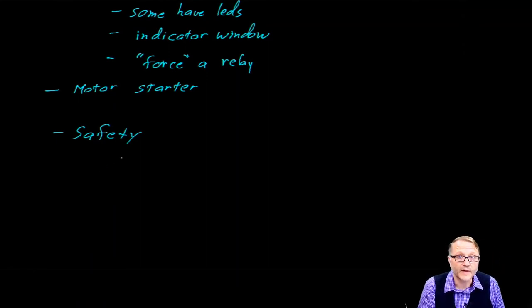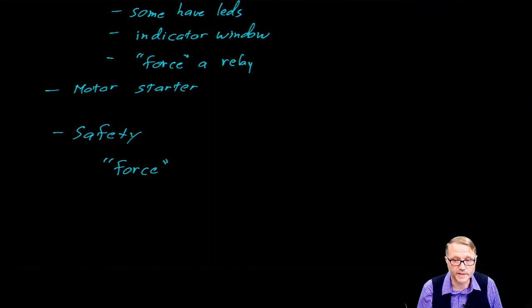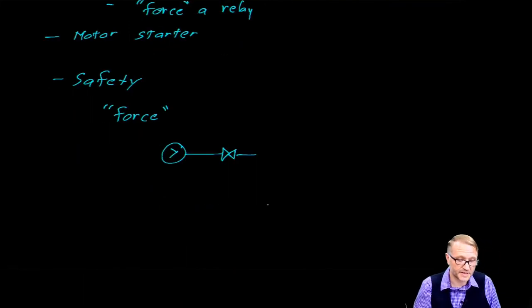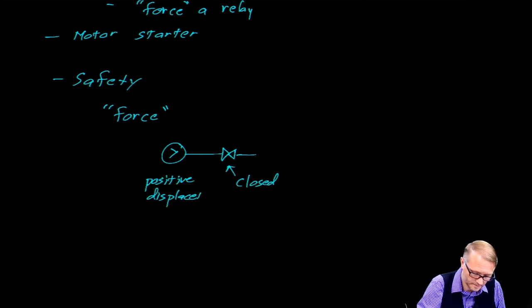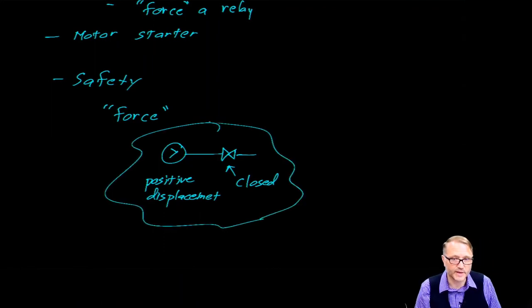Now look, the fact is you've got to be really careful if you're going to go force a relay. You need to know exactly what's going to happen before you do this. For instance, let's say we had a pump and that pump was operating against a valve. And just to make the situation worse, let's assume this is a positive displacement pump and this valve is closed. Now, if you were to go to that motor starter and force it by pushing the plunger in, you're in trouble. Something is going to break in this situation. A positive displacement pump will have a tremendous pressure and you'll rupture the pump, you'll rupture the valve, or you could actually hurt somebody in the process.